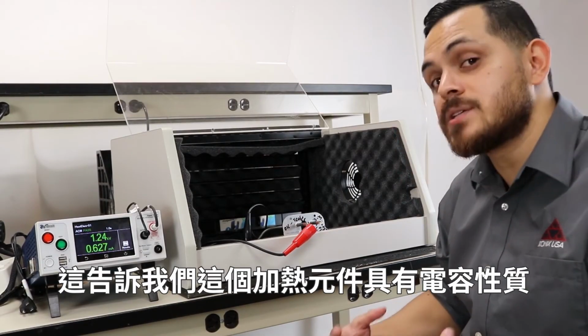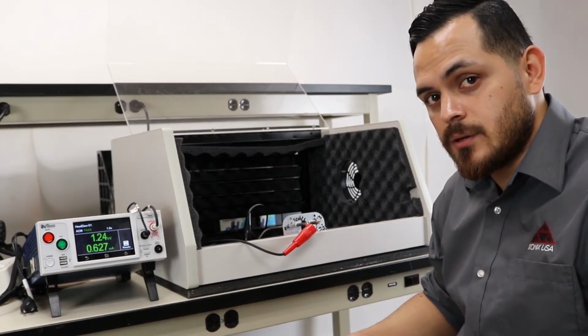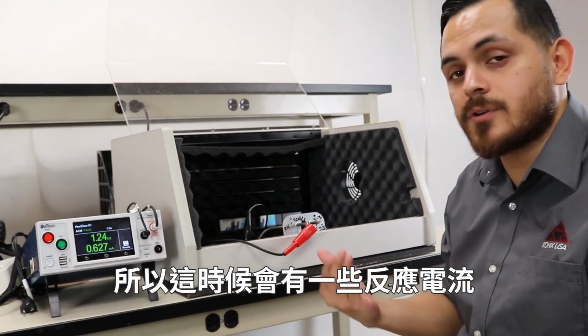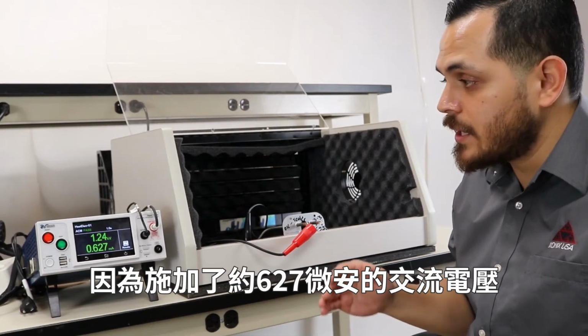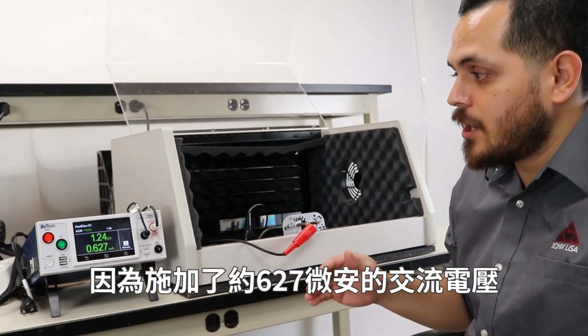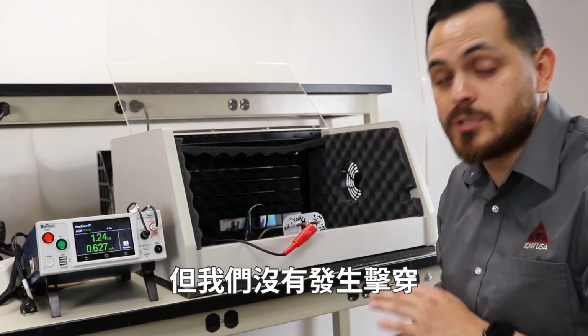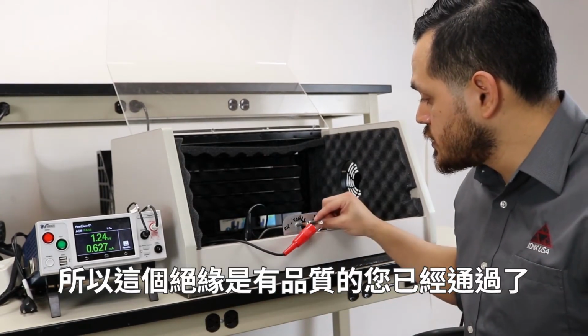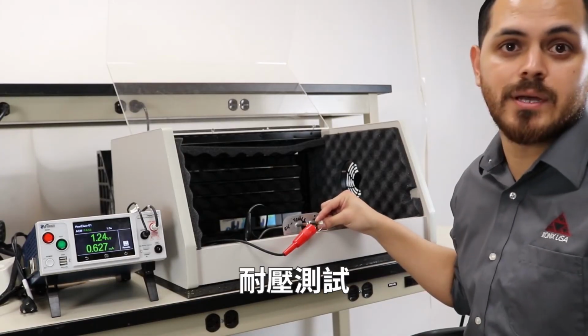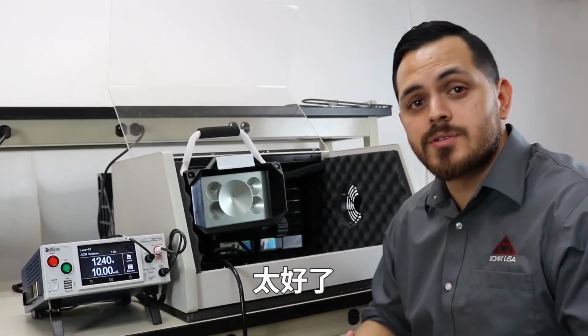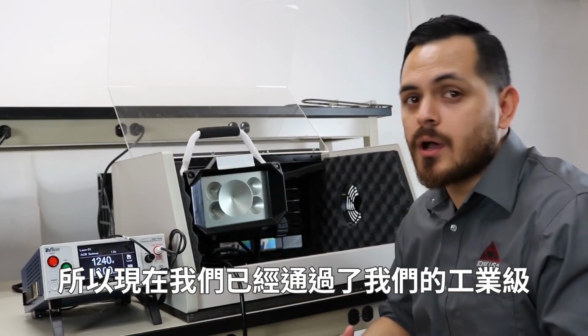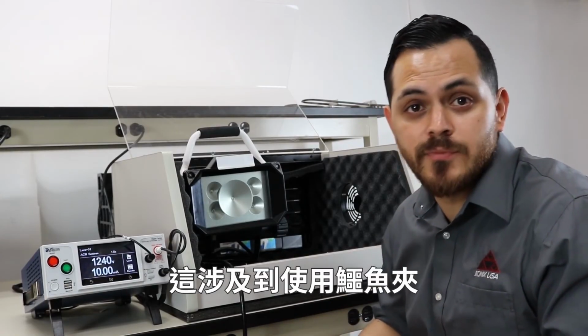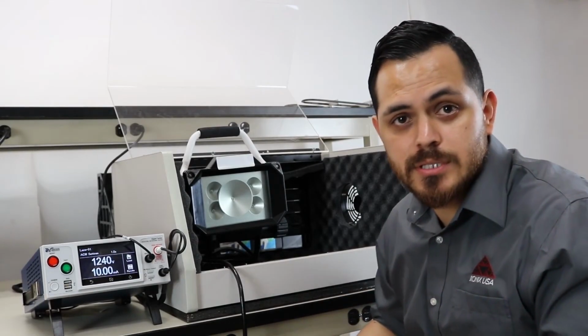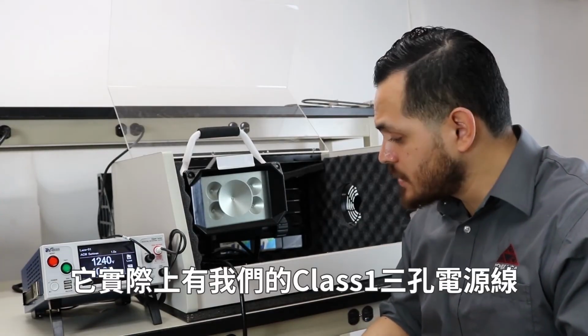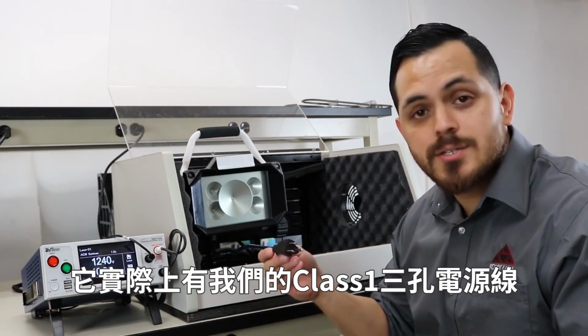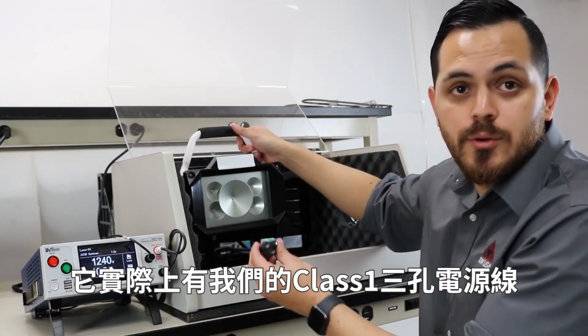That tells us that there's a capacitive nature to this heating element, right? And so there is some reactive current occurring when you apply AC voltage at about 627 microamps, but we do not get a breakdown. So this insulation has quality and you've passed your Hipot test. Great, so now that we've passed our Hipot test with our more industrial heating element, which involved using the alligator clips, let's move on to something a little bit more common that actually has your class 1 3-prong line cord.